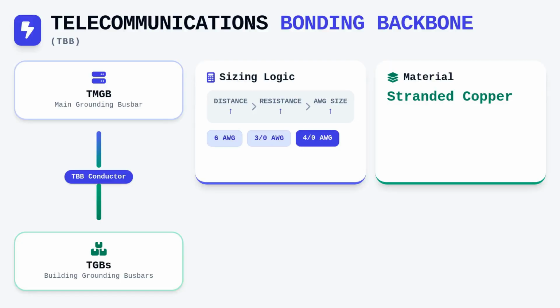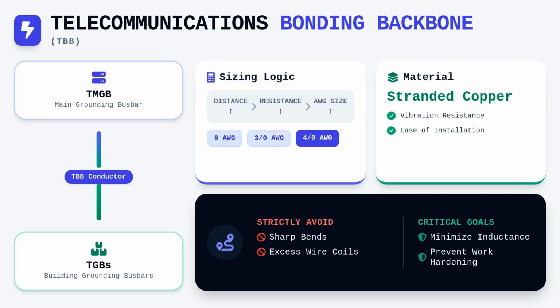You must ensure that this conductor is stranded copper as it offers better vibration resistance and ease of installation compared to solid conductors. The TBB should be installed in a manner that avoids sharp bends, adhering to strict minimum bend radius limits for grounding wire to prevent mechanical stress that can lead to conductor work hardening. Because this backbone carries circulating currents during electrical faults, the physical routing must remain as straight as possible and avoid excess coils of wire, which would otherwise introduce unwanted inductance into the circuit.